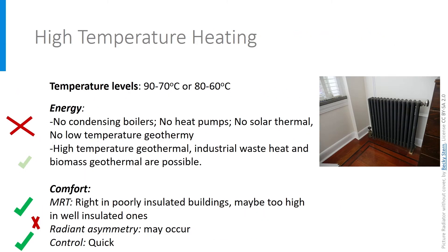Although there is no strict definition, we consider emitters to be at a high temperature when the supply temperature is above 80 degrees Celsius and the return temperature above 60. In Europe, 90 supply and 70 degree return was quite standard in the past. 80-60 is also common. You see on the picture a typical high temperature radiator.